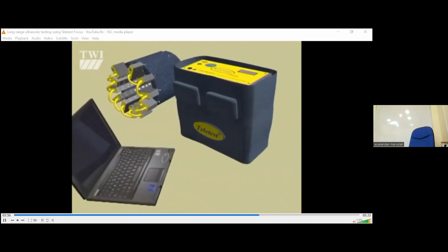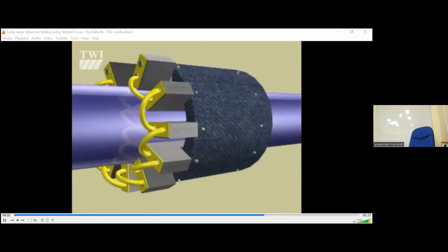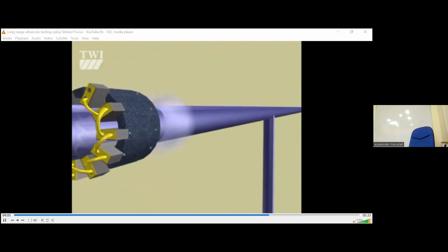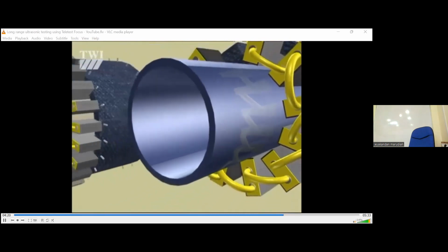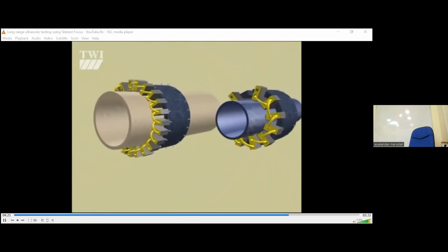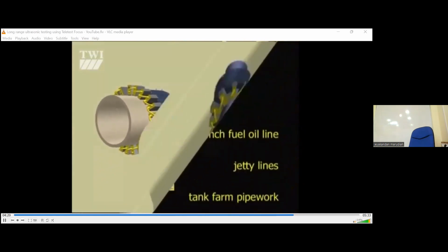So a special flaw detector is required. That's what this box does over here. The low-frequency sound can travel long distances along the pipe, several hundreds of meters under ideal conditions. So by transmitting the sound a long distance, we can examine large lengths of pipe in one go. Because it's a modular system, we can modify the transducer collar and test pipe upwards of 2 inches diameter using the same system for all sizes.